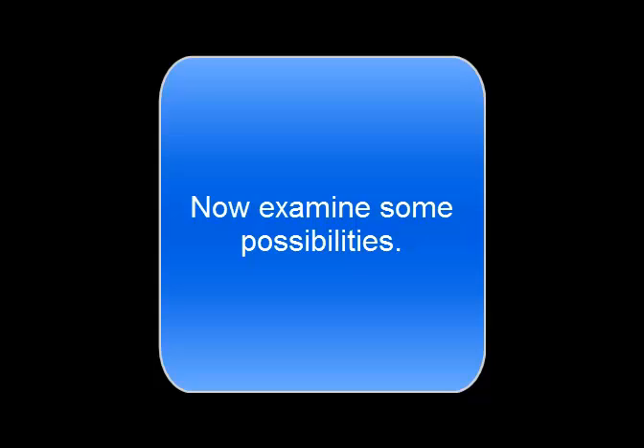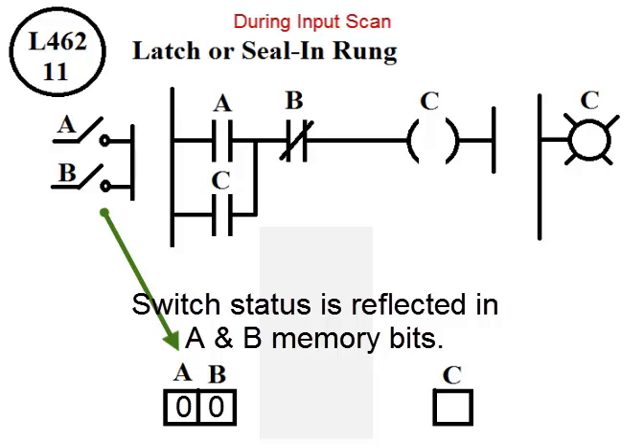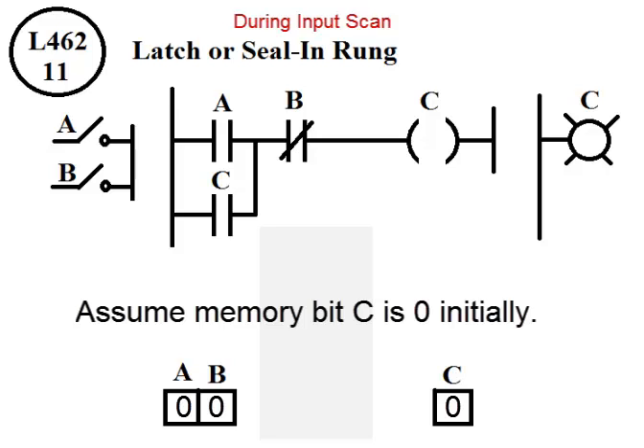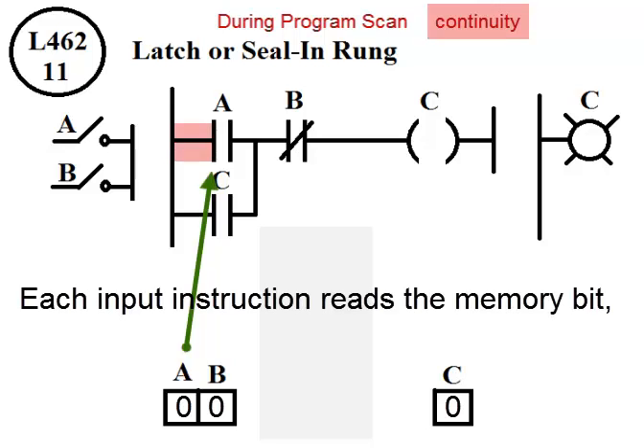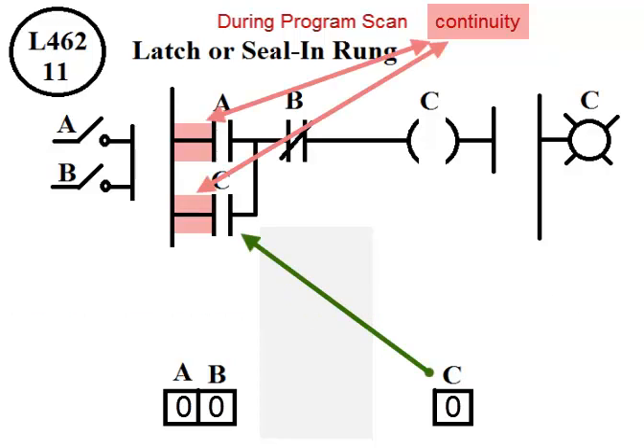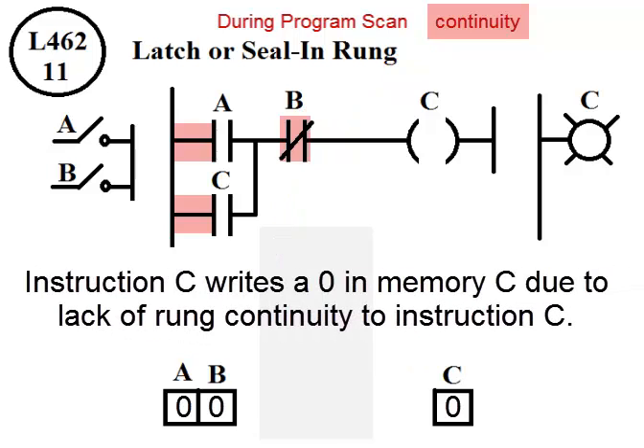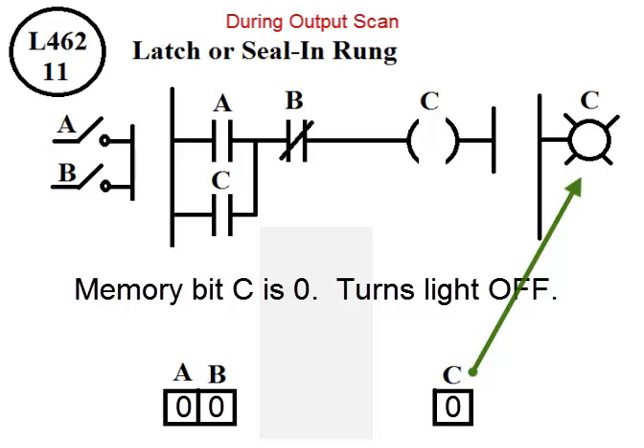Now examine some possibilities. During input scan switch status is reflected in A and B memory bits. Assume memory bit C is 0 initially. During program scan each input instruction reads the memory bit and results in rung continuity from left to right. Instruction C writes a 0 to memory C due to lack of rung continuity to instruction C. Memory bit C is 0. The light turns off.